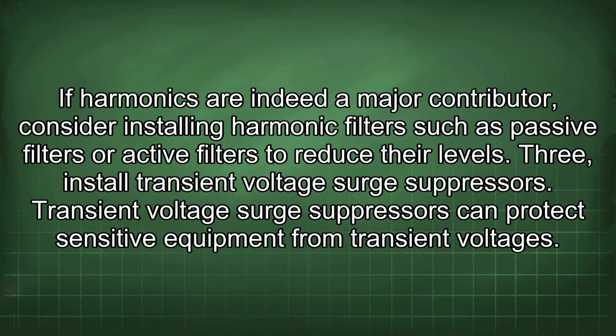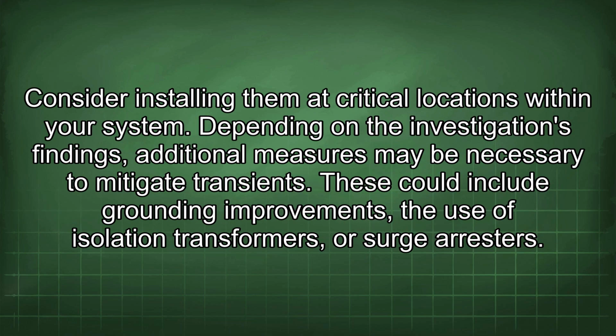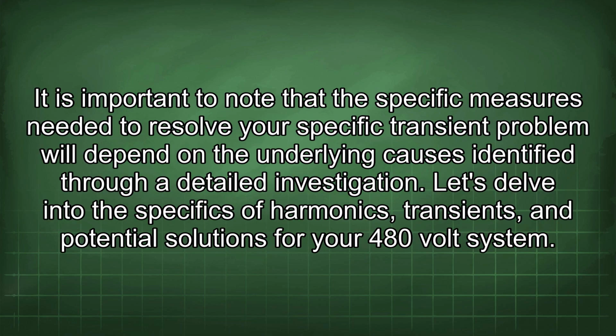Transient voltage surge suppressors can protect sensitive equipment from transient voltages. Consider installing them at critical locations within your system. Depending on the investigation's findings, additional measures may be necessary to mitigate transients. These could include grounding improvements, the use of isolation transformers, or surge arresters. It is important to note that the specific measures needed to resolve your specific transient problem will depend on the underlying causes identified through a detailed investigation. Let's delve into the specifics of harmonics, transients, and potential solutions for your 480 volt system.